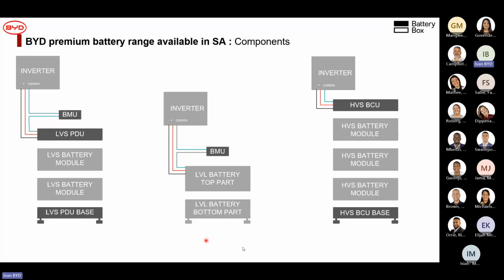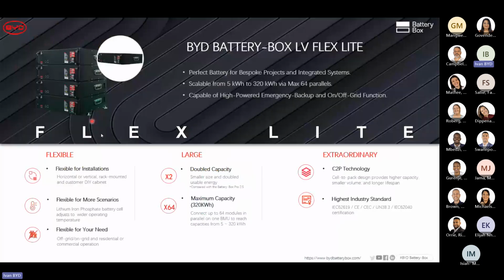Just in terms of how to wire your batteries, on a high voltage, every high voltage tower needs a BCU, and then the battery modules. Then for the LVLs, you need 1 BMU per battery bank. And then for your LVS, you need 1 PDU per tower and 1 BMU per battery bank. Here's a quick summary of the specifications for the BYD Flex Lite.